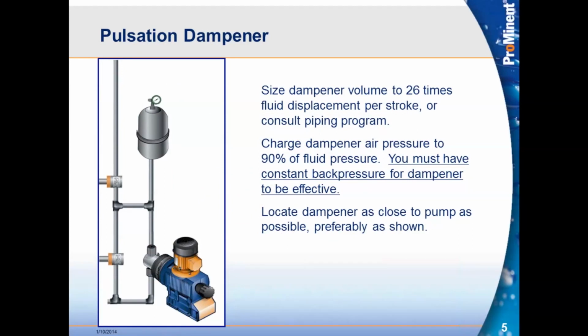You can see the arrangement here. The way the pulsation dampener should be installed is in direct line with the discharge valve of the pump. We like that flow to go directly up and hit right into the bottom of that bladder that's inside of that pulsation dampener. And then you can see on the left at the top is our back pressure valve. That back pressure valve is going to dictate the pressure that we're set at, and then we're going to charge the gas in that pulsation dampener to 90% of what we have that back pressure valve set to start at. We would need a gauge in line. That gauge is a helpful tool here as well because we can see the pulsation on that gauge. So if it continues to pulsate a lot, even if we're charged to 90%, we can very carefully, very slowly bleed some of the air, some of the charge out of that bladder to help smooth out that pulsation that we might be seeing.